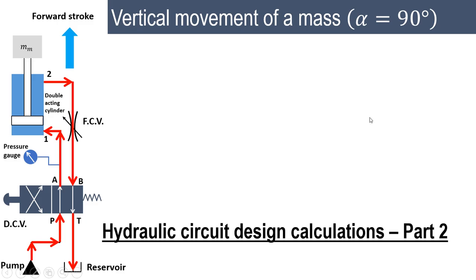In this video we'll try to understand how to design a hydraulic circuit in the case of a vertical double acting cylinder. It is the vertical movement of a mass. Since the mass moves vertically, the value of alpha, measured from the x-axis, will be 90 degrees. We need to understand what will happen in this particular case.